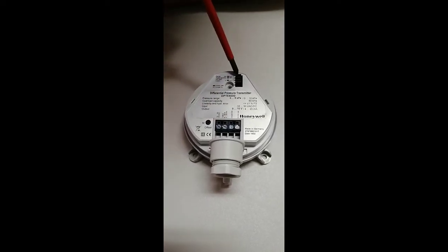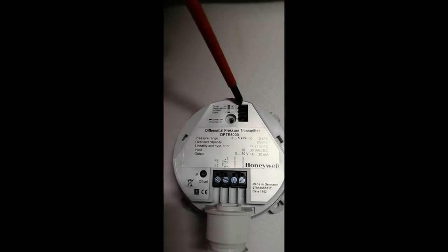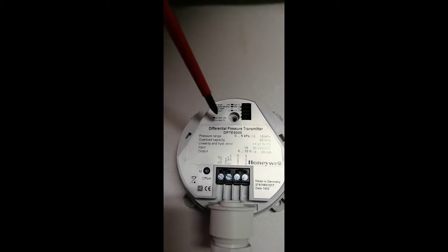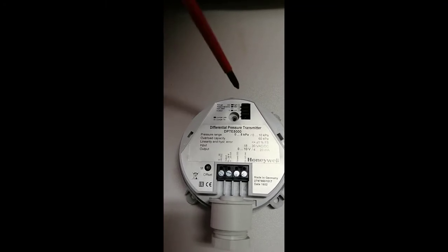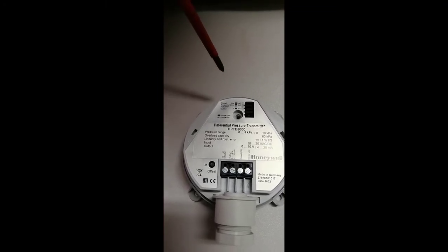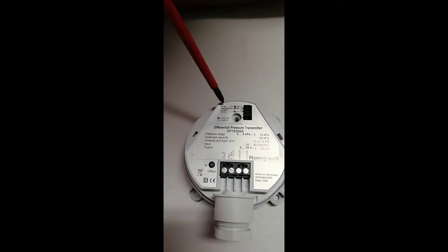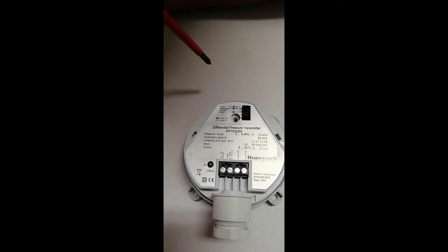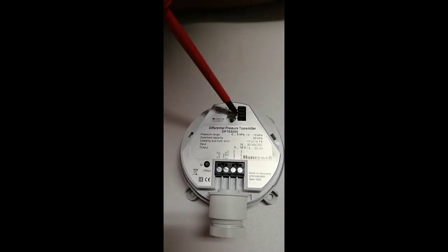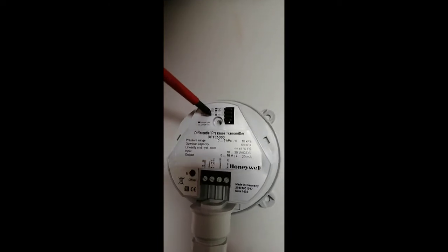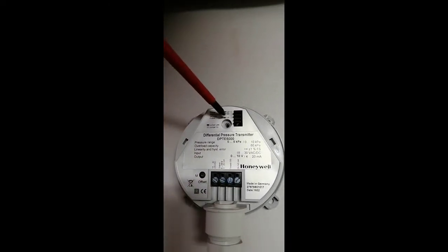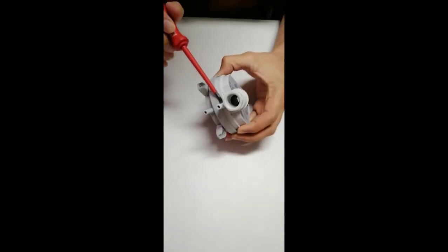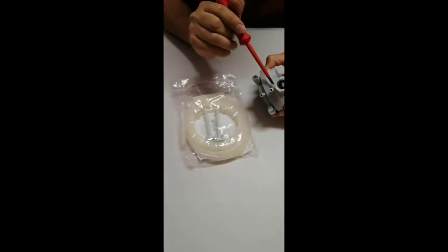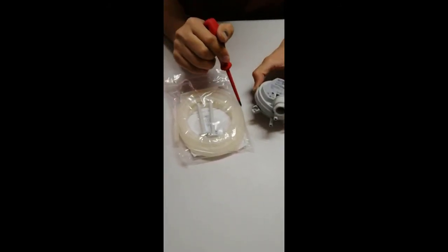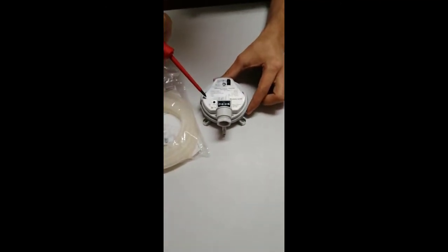And then here we have different jumpers to select the range. For example, we can select low range or high range. In low range it will detect from 0 to 5 kilopascal, and in high range it will detect from 0 to 10 kilopascal. And even we can select the response time. We want it to respond slow or fast. And then output signal we can select from here using this number fourth jumper, that we want voltage signal or milliampere signal. So here we have two ports, positive port and negative port. So using this pipes are connected to these ports, and then we install this inside the ducts or wherever our application is. So this is how we make connections for differential pressure transmitters.